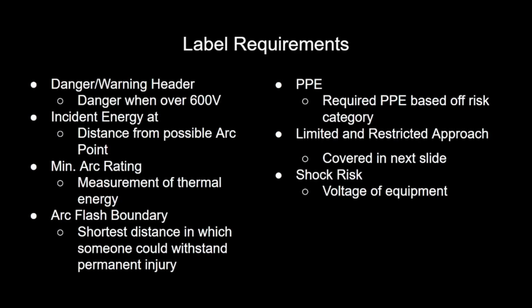Arc flash boundary is the shortest distance at which someone could withstand permanent injury. PPE: there's a list of required PPE based off the risk category on every arc flash label. Limited and restricted approach, I'm going to cover a little bit more in the next slide, the difference between the two. And then the shock risk is just the voltage of the equipment you're working on.